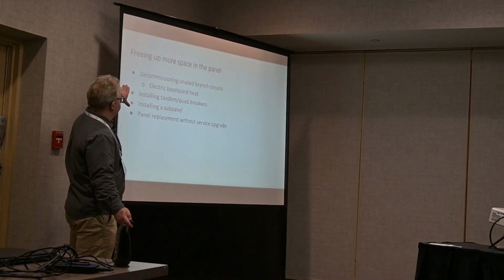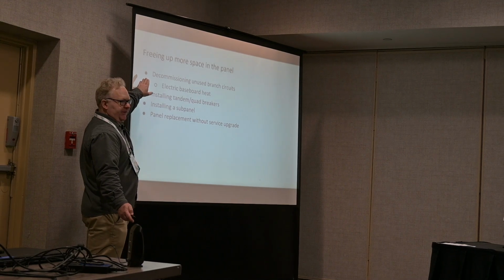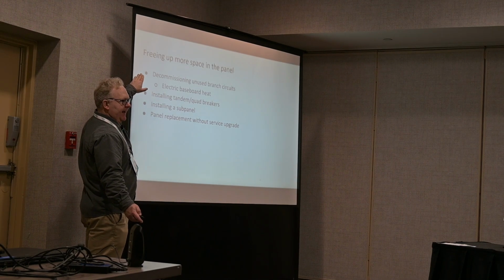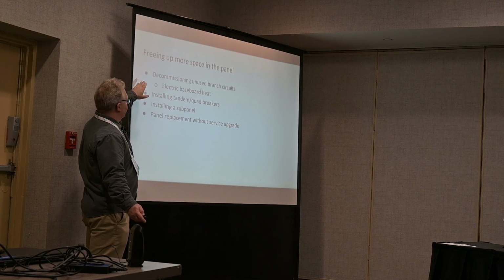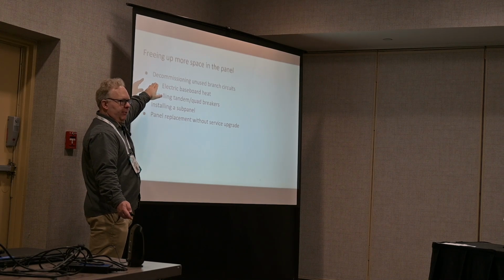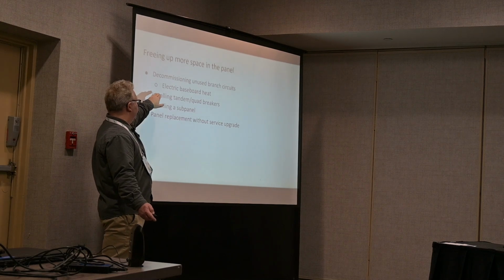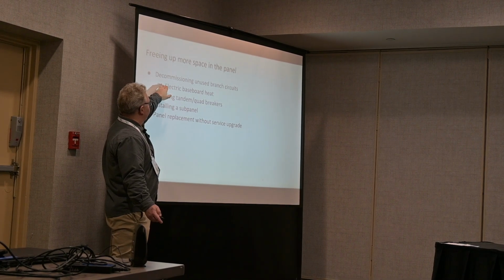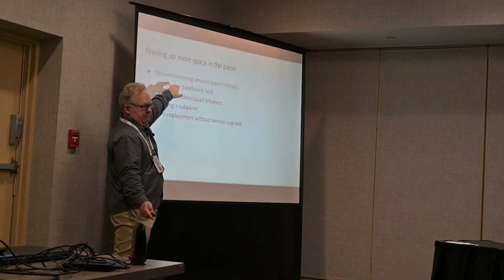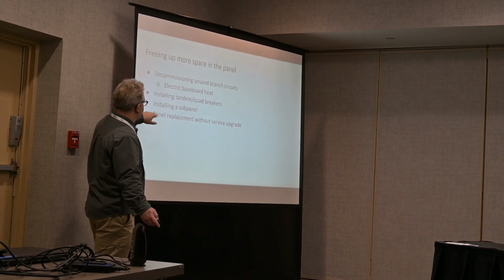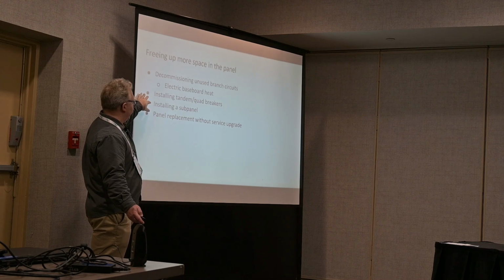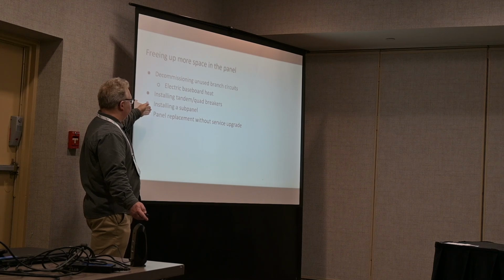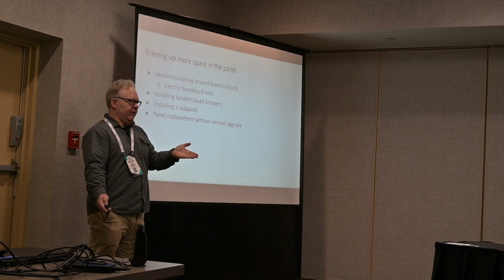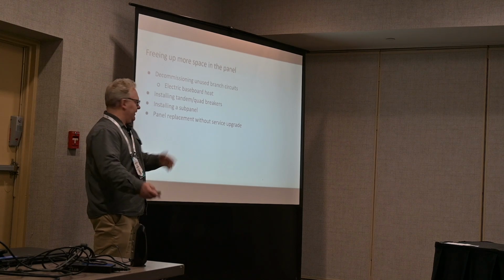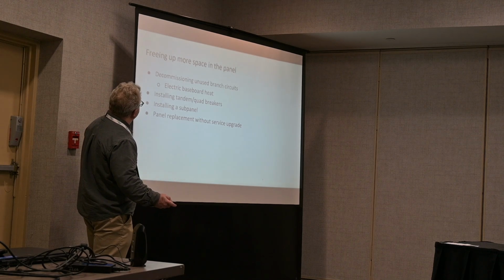Options for freeing up more space in the panel. So this isn't about amps, it's just about spaces. If we have unused branch circuits, for example, if we're replacing electric baseboard in a room with a ductless heat pump, we can use those spaces. We can install tandem and quad breakers, which I'll talk about in the next slide. We can install a sub panel. And there's times when we don't want to upgrade the whole service. We just need more spaces, so we can upgrade the panel and get more spaces that way.